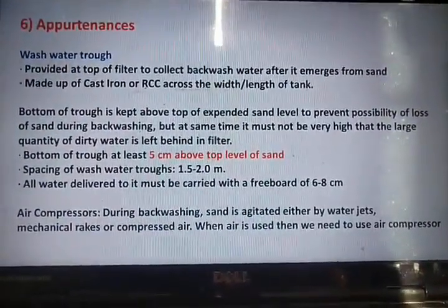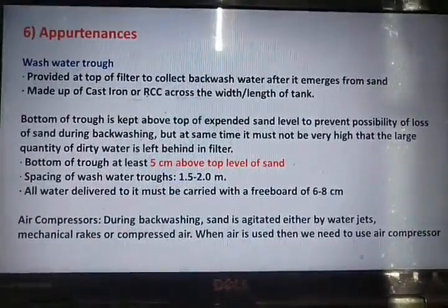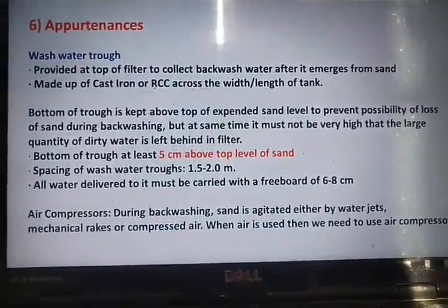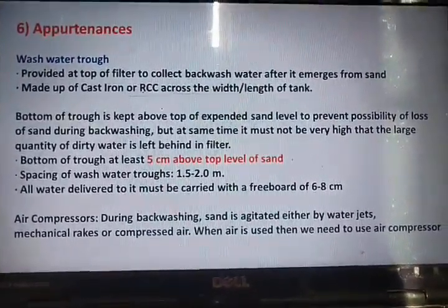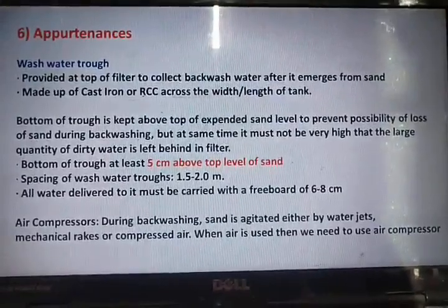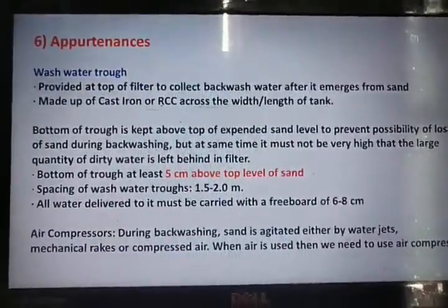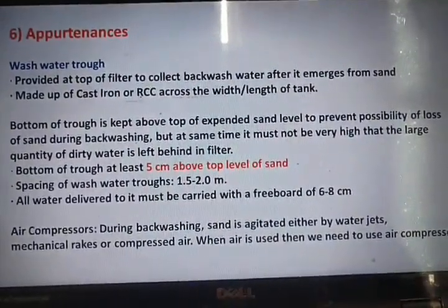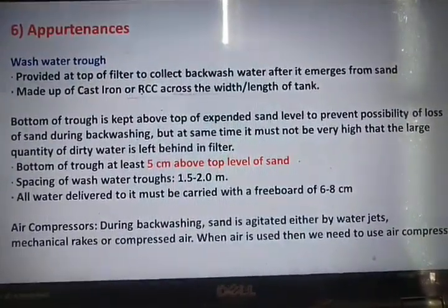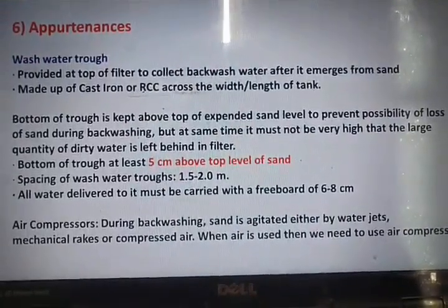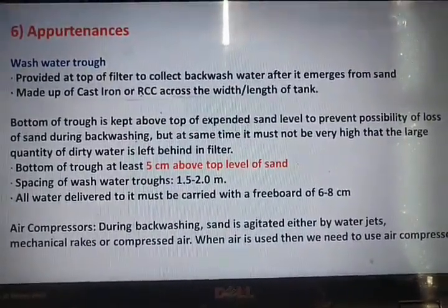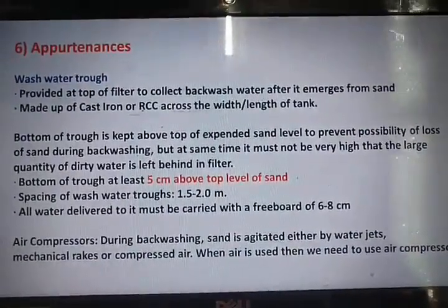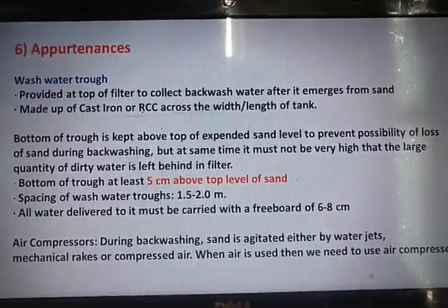Okay, then the different appurtenances, we have something called a wash water trough. Okay, I will show you in the diagram what the wash water trough is. So here these wash water troughs are provided at the top to collect the backwash water. That is, this filter requires frequent cleaning, like in the order of 1 to 3 days, depending upon the type of effluent water quality. So we do frequent backwashing. When you do the backwashing, the sand bed will expand and the water will overflow from the sand bed filter, and it has to be taken out.